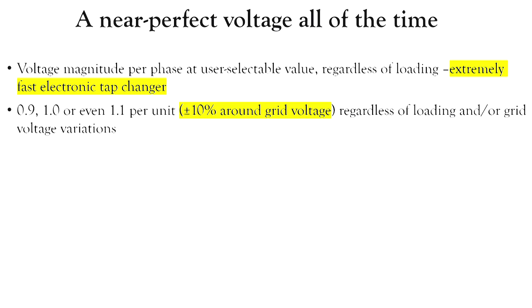That voltage can be boosted by at least 10% continuously to a value of 11 or 10.5 plus another 1,000 volts. So we can boost it easily to 11.5 roughly. Or if voltage is too high, even reduce it continuously. And that is not done by a UPS. What is so beautiful about these solutions and these very, very fast power electronics and signal processing nowadays available, it can be done per phase, of course, but also in terms of phase angle.